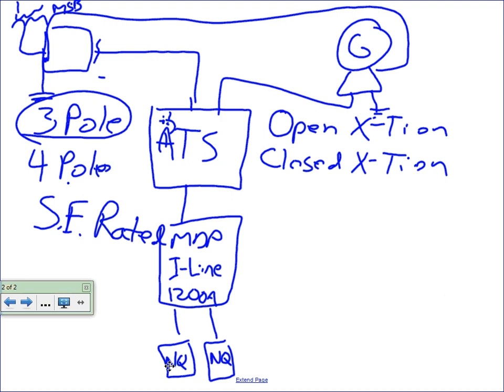Now, this is Switchgear. It serves the same purpose as the switchboard, but this has a different UL. This is 1558. The difference with this product is, if you open up that front screen, it's really hard to tell, but on a switchboard, most of the terminations are available from the front. So we can build it for front access only, so you can slide it against the wall and still get to all the terminations within the product.